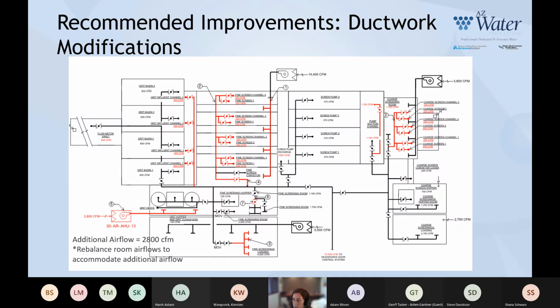I realize what's on the screen is a lot, but it's mostly to show you the extent of the foul air duct modifications and supply air modifications we recommended to the system. I want to point out that although it looks like we added a lot of ductwork, we did not add a significant amount of airflow to the carbon system. What we intended to do was actually redirect some of the flows, and I can walk you through that.